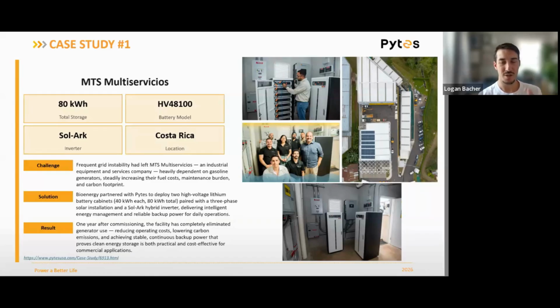High voltage batteries, given their different connection method, are a lot more sensitive to things like over voltage and under voltage. Sometimes even if there's one battery module in the stack, or just one cell within a module that goes over temp or under voltage, it knocks out the whole stack. So when we do these high voltage systems, the first part of my answer is that we always have communication - that's basically a requirement.